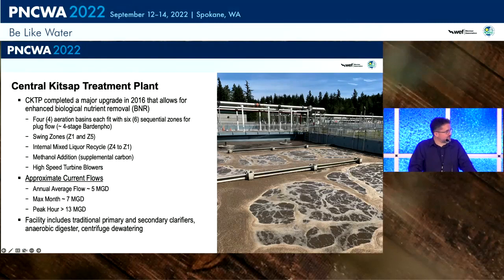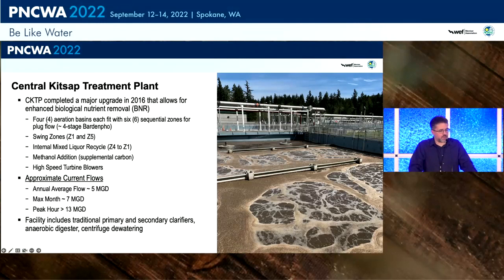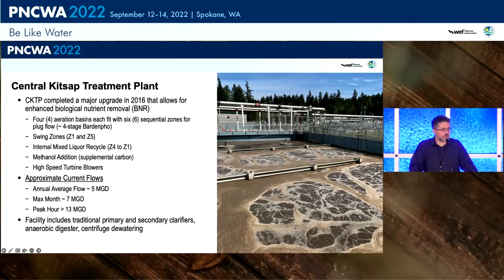Annual average flows are more like three to five MGD, with some peak month and peak hour flows over 10 to 13 MGD. The facility as a whole has traditional primary and secondary clarifiers, mesophilic anaerobic digestion, and centrifuge dewatering. The key thing to note is that since the upgrade, the plant was preparing itself for nutrient removal that everyone knew was coming, but it had not really commissioned itself to operate in full BNR mode.